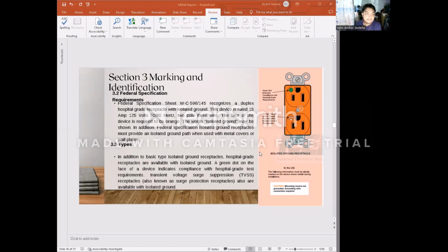Now, the federal specification requirements. It recognizes a duplex hospital grade receptacle with isolated ground. This device is rated 15 amperes, 125 volts, and 50 to 60 hertz, 2-pole, 3 wire. The face of the device is required to be orange, and the words isolated ground may be shown in addition. Federal specification isolated ground receptacles must provide an isolated ground path when used with metal covers or wall plates.